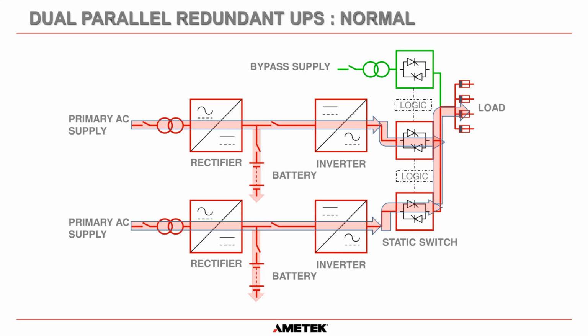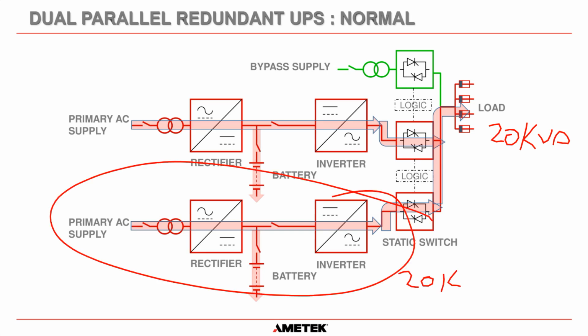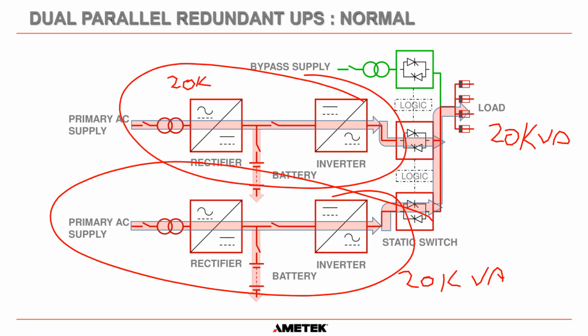And now we're going to mention the different topologies. In other words, it's a fancy word for saying how you can connect them together to give you some form of redundancy. So what we've talked about is a single UPS. And now in this screen here, we have what's called a dual parallel redundant UPS. Now, the important thing to remember to start off with, let's say your load design, say we needed 20 kVA of power to the load, then what you have to do is this UPS down here has to be able to supply 20 kVA. And this UPS here needs to be able to supply 20 kVA.